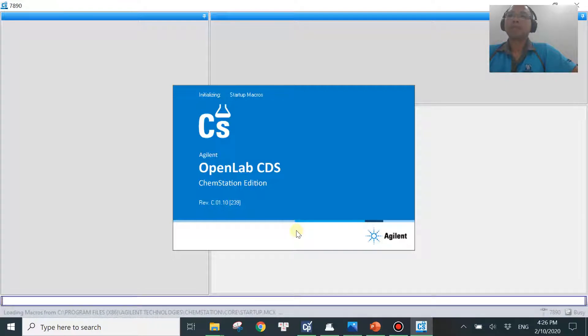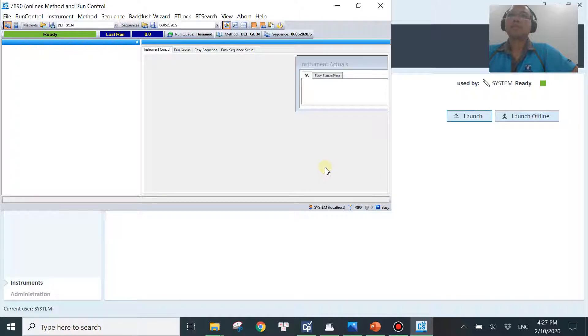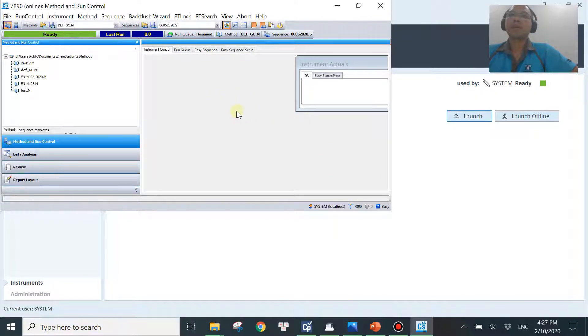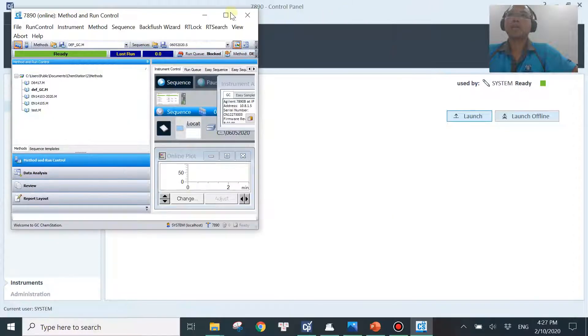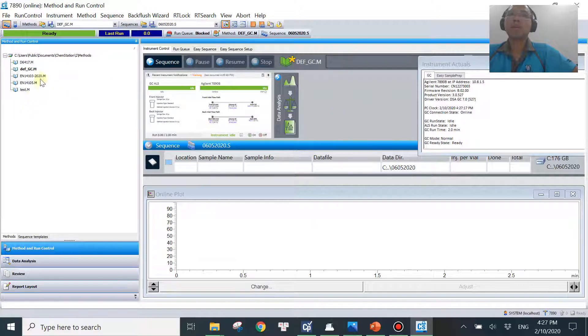It will take a few seconds to launch. No error — that's good. There you go. You can see the software is able to launch normally and it loads this method out to the GC. That's how you fix that error if you are using a new version like the one I'm using.